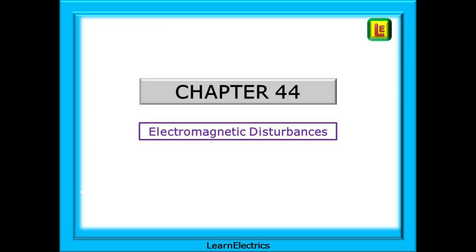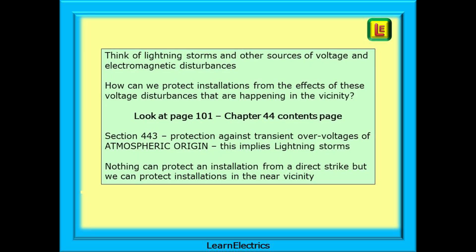Now look at Chapter 44 — electromagnetic disturbances. Think of lightning storms and other sources of voltage and electromagnetic disturbances. How can we protect installations from the effects of these voltage disturbances happening in the vicinity of the installation? Look at page 101, the Chapter 44 contents page. We can see section 443: protection against transient overvoltages of atmospheric origin, implying lightning storms. Nothing can protect an installation from a direct strike, but we can protect installations in the near vicinity from these voltage disturbances, which can be significant.